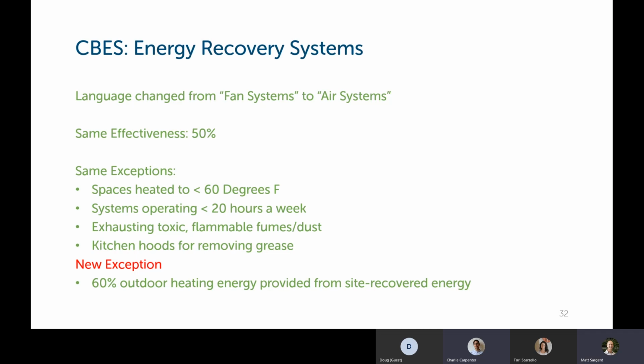Hold on here. For energy recovery systems in the commercial code, the language has changed somewhat from fan systems to air systems, which I'll describe what a fan system is later in this presentation. So that is a somewhat important distinction with the new version of the code. Besides that, the requirements are mostly the same for energy recovery systems. The effectiveness of the system is still at 50%, and there are mostly the same exceptions.